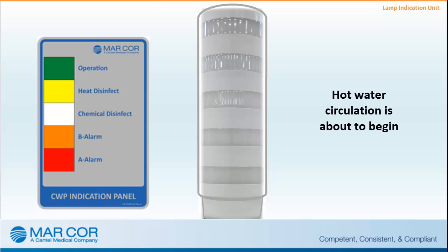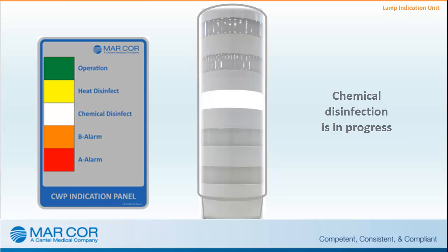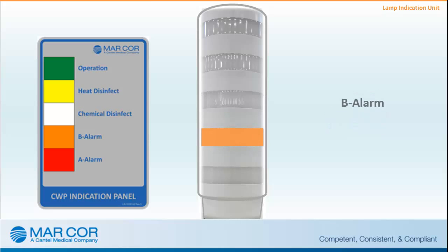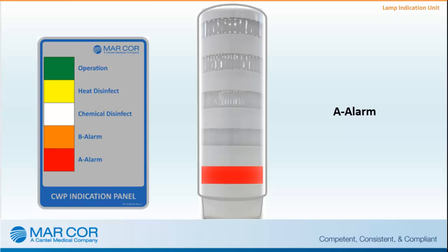A blinking yellow light is a warning that hot water disinfection is about to occur. A steady white light indicates a chemical disinfection is in progress. A blinking white light indicates that chemical disinfection is finished but the residual test has not yet been performed and verified by entering the operator's code. A blinking orange light notifies the operator that an alarm type B has occurred — the RO will not stop water production. A steady orange light indicates the B alarm has been acknowledged but the cause still remains; an example of a B alarm is battery-low PLC. A blinking red light indicates an alarm type A has occurred — the RO will stop water production. A steady red light means the A alarm has been acknowledged but the cause still remains; an example of an A alarm is high conductivity.